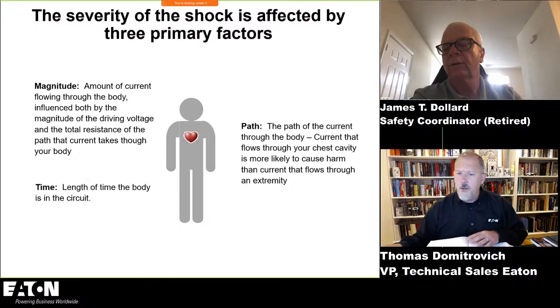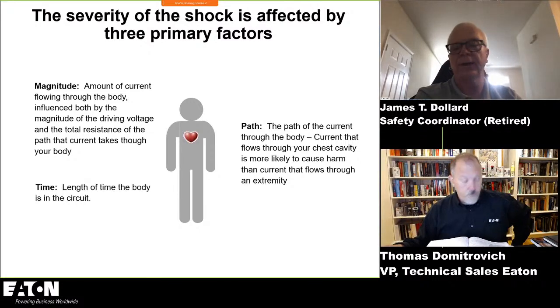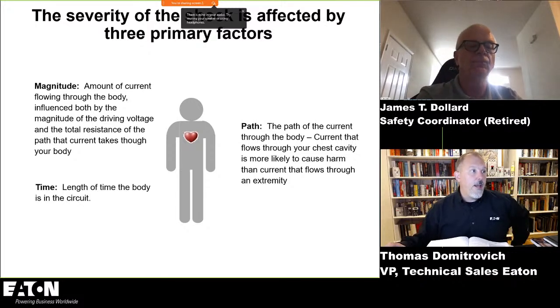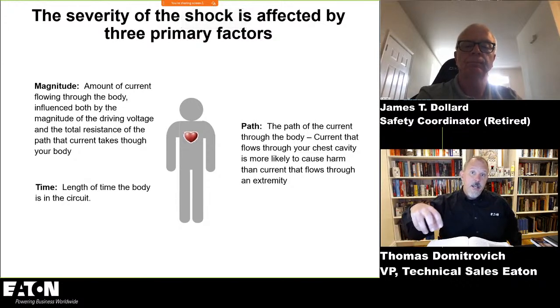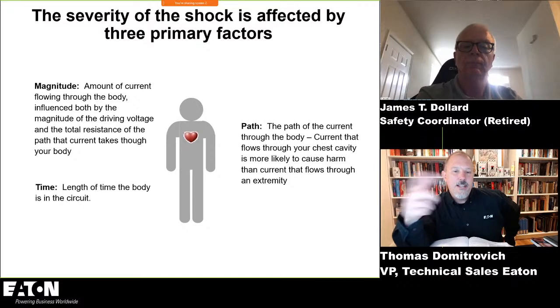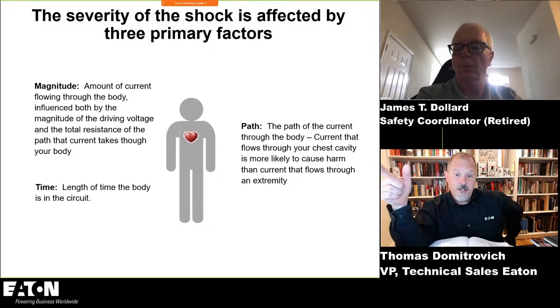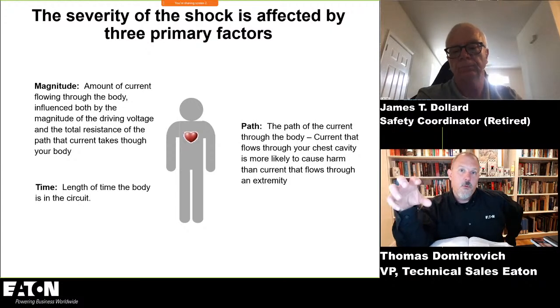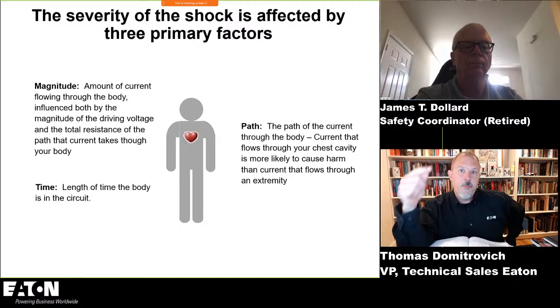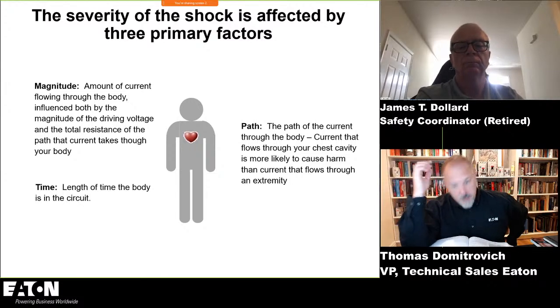So now, when you did GFCIs the other day, I wasn't able to tune in. Did you get into GFCIs that are listed as portable with open neutral protection? We did. We had a discussion about how they're tested, and we didn't go as deep. Nihad and I were talking afterwards that we're going to probably have to do another session because he wanted to go a little bit deeper, as did I, into some of that testing that recognizes the open neutral on the primary, which is why we check our extension cords and things of that nature, because we have to be able to detect that. And there was another one too, I think a grounded neutral in different locations as well.